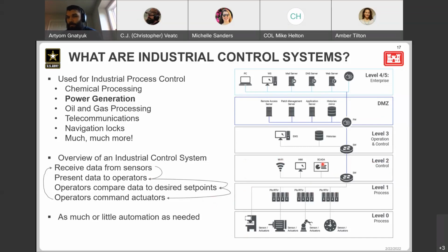The SCADA would be maybe some sort of supervisory control - maybe some automation we have to program for the operator to do some sort of control actions on their behalf. Level 3 is a bit higher level, more so for overarching plant controls versus just control per device or per actuator. There might be some historical data we want to store on the historian, or an energy management system, or maybe an overarching plant management system.